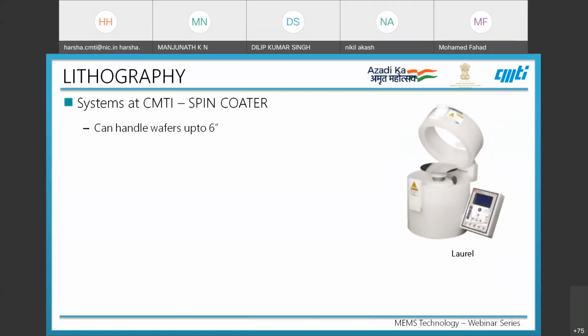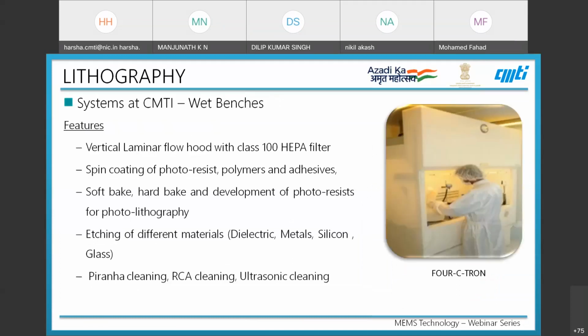Then we also have a spin coater from Laurell which can handle wafers up to 6-inch. Then there are wet benches. All the baking, development, and cleaning processes are done under the fume hoods or the wet benches. They come with a vertical laminar flow hood with a class 100 filter, and even spin coating of photoresist is done inside the wet bench. Etching of different materials such as dielectric, metal, silicon, glass, etc. is also performed. Piranha cleaning, RCA cleaning, and ultrasonic cleaning can also be performed using these wet benches.